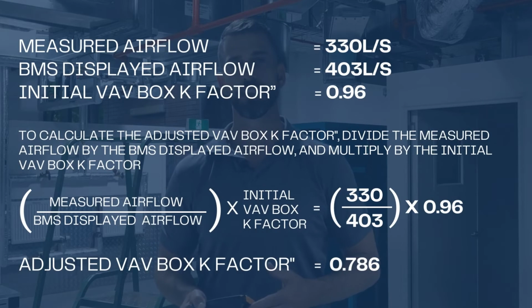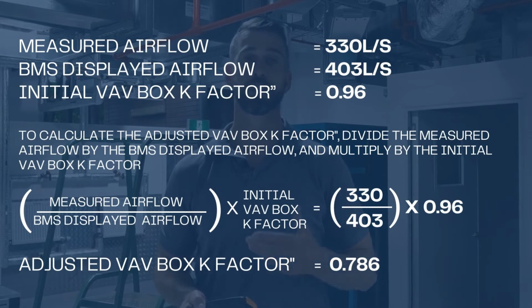So we've measured our VAV airflow at 330 litres a second. The BMS is indicating that it's at 403 litres, so it's out of calibration. The existing K factor is 0.96. So to arrive at our new factor, we simply get our measured airflow divided by the existing BMS airflow and multiply it by the K factor. Once we do that, we arrive at a new K factor of 0.78.